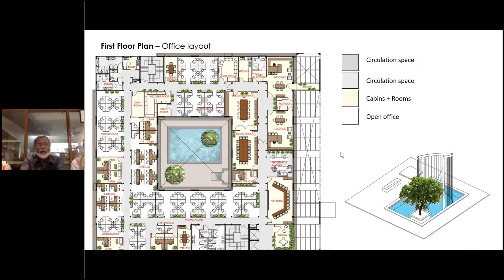You'll notice this building doesn't have suspended ceilings over the working areas. There's a ceiling over the passage where the return air ducts occur for fresh air supply, but elsewhere the ceiling has to stay exposed, because that's the cool surface, and the body of the occupants needs to be able to see the ceiling. It's only when the body sees the ceiling that the coolth is felt as a radiant effect. The body radiates heat towards the slab, and the heat is carried away by the chilled water pipes. So you have to devise a system without suspended ceilings, yet with all the modern services still within it.